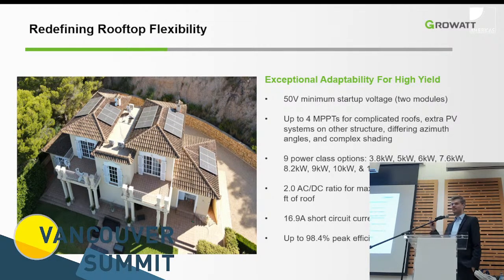And with the load side connection these days, the bus bar rating in a residential dwelling is restricted to 125% of the bus bar rating, which means if we have a 200 amp service and a 200 amp bus bar rating, 200 amps multiplied by 1.25 gives us 250. We subtract the incoming service of 200, which gives us a 50 amp breaker. With a breaker sizing factor of 0.8, that gives us 40 amps continuous output current. And 40 amps multiplied by 240 volts gives us exactly 9.6 kilowatts. And 9.6 kilowatts is not 10 kilowatts.